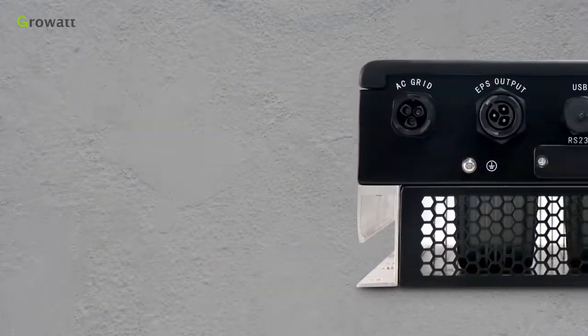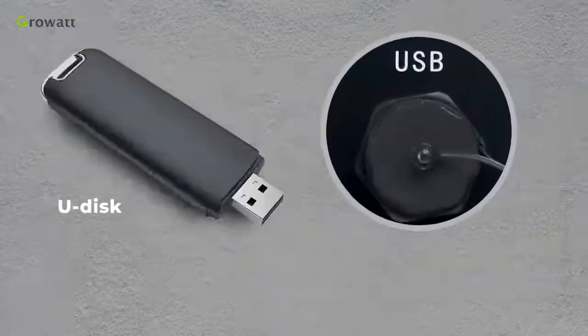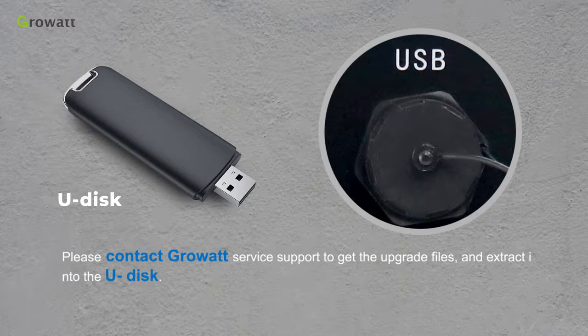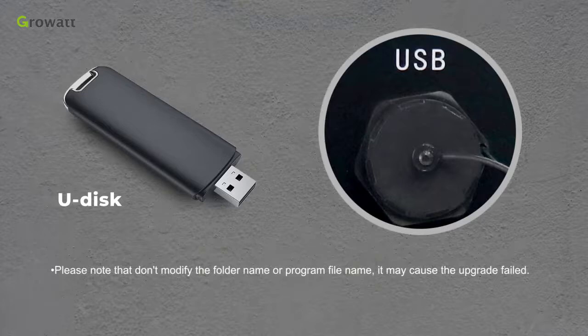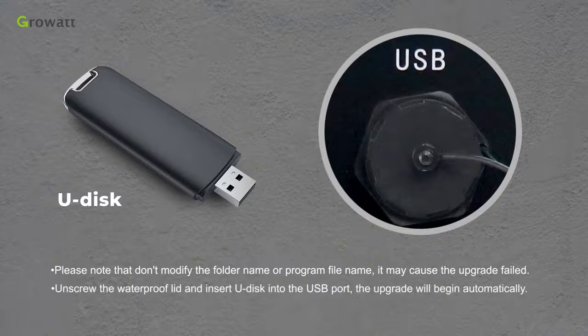User can upgrade inverter's firmware via the USB port by using a U-disc. Please contact Growatt service support to get the upgrade files and extract into the U-disc. Please note that don't modify the folder name or program file name. It may cause the upgrade failed. Unscrew the waterproof lid and insert U-disc into the USB port. The upgrade will begin automatically.